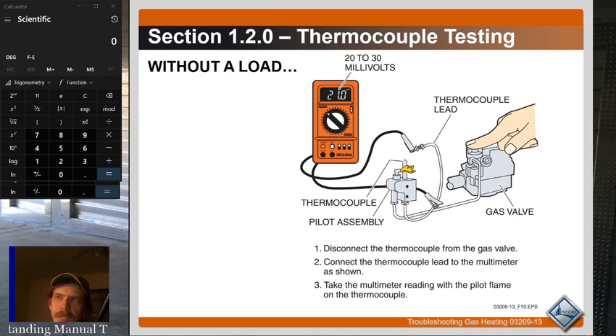But anyway, that's how you properly diagnose a thermocouple. I can tell you real world, basically, if you light the pilot, and you hold that knob down for about 30 seconds, and then you let go and the pilot immediately goes out, your thermocouple is bad. That's why I haven't used one of those adapters in years, because you kind of get good at just saying, nah, the thermocouple is no good. And if you're wrong, it costs you $12, and you have to bite the bullet and say you were wrong and it was actually the gas valve. But 9.5 times, if not 9.9 times out of 10, if the pilot won't stay lit after the thermocouple's had plenty of time to heat up, then it's the thermocouple that's bad.